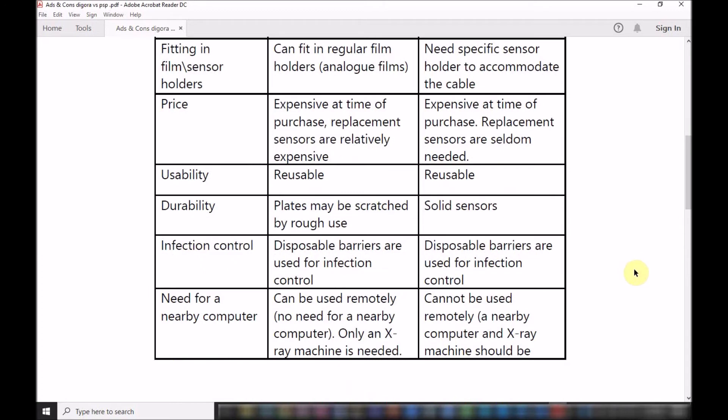Plates when it comes to durability, plates may be scratched by rough use, so you need to be gentle with them. These direct sensors are more robust. They are solid. The only thing that you need to take care of is the cable. Please don't bend those cables because bending the cables will definitely harm them. The sensor will remain useful but the image cannot be transferred properly to the computer, and then you need to replace the whole thing. You cannot replace the cable only, it comes all in one piece.